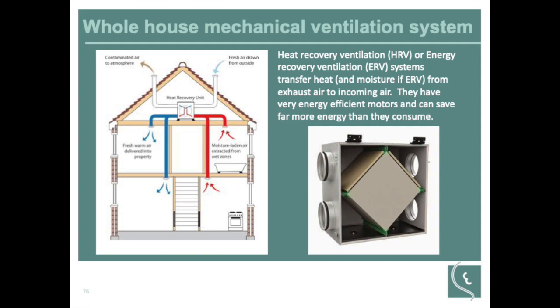I think probably a lot of people just see a continuous, for lack of a better term, bathroom exhaust fan and then a duct cut in to bring in the fresh air. One of the challenges with that goes back to building pressure, where these are very good about balancing that supply and exhaust air. If you don't, you can end up with building pressurization and sucking in unconditioned air in places you don't want it. So, one of those best practice versus reality things. This is what one of those looks like.